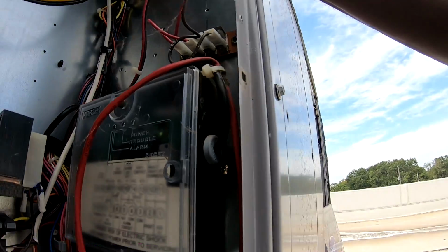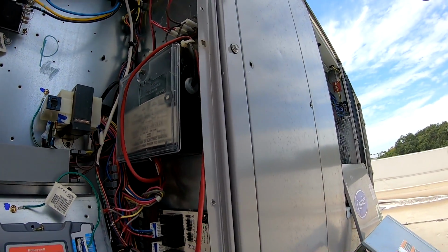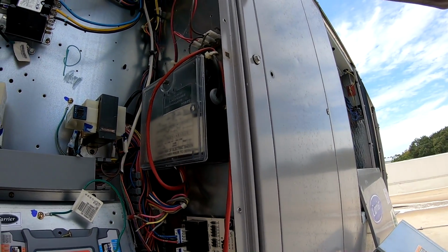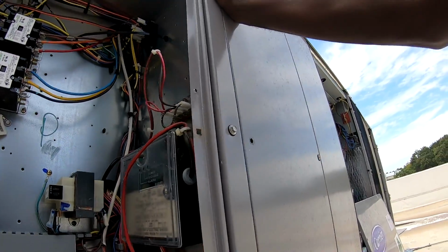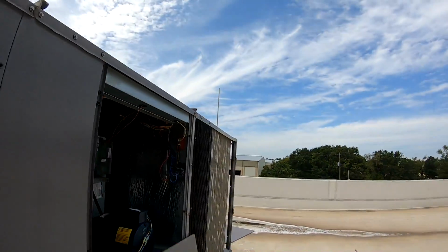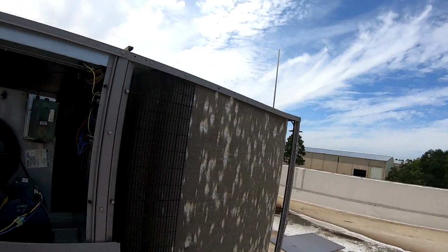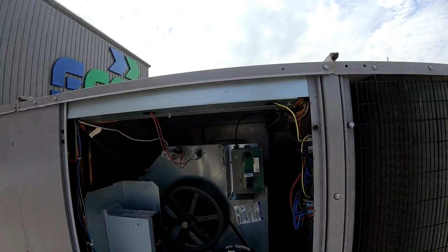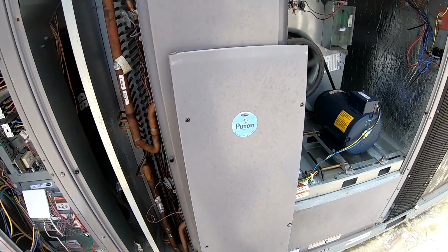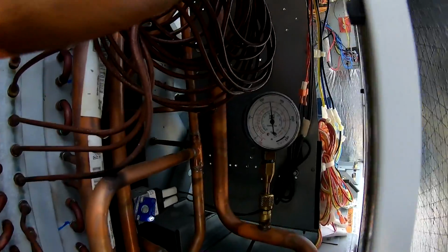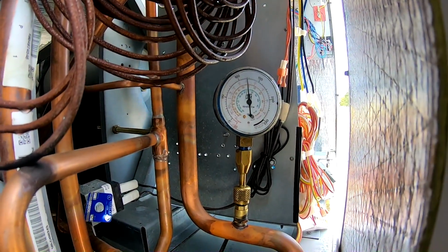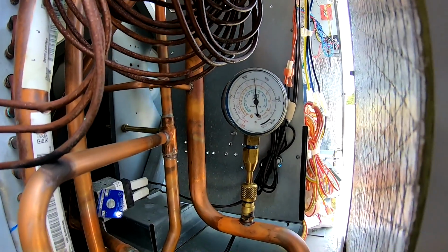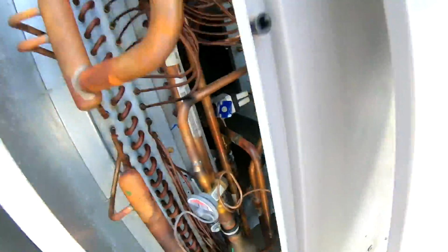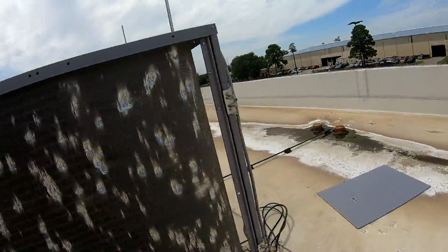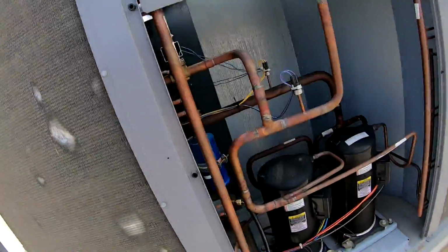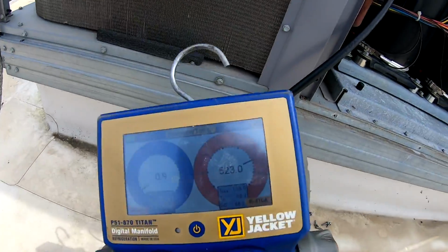Got a green light there, man. We got power. All right, so I'm gonna give it a minute to call for cool. All right, so I got the unit running. They got the suction valves on this side of it, so I got my little snug right there. See, I'm reading 150, which is cooling, but I got my high side hooked up to the discharge line.